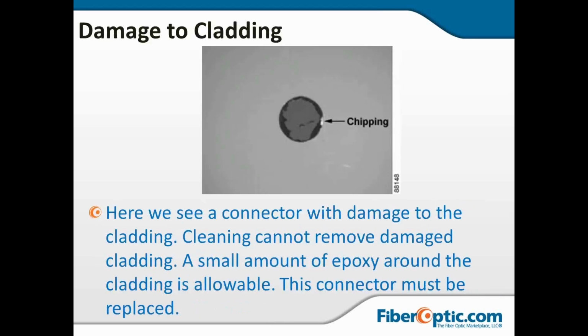This one is chipped, as you can see on the right-hand side of the image, and it's got a huge epoxy ring telling me that this is a hand-polished connector, and that they're trying to polish down below the end face of the ceramic ferrule, and that one will never be cleaned. You see an image that looks like this, just go ahead and replace it, because no amount of cleaning or polishing is going to fix that.